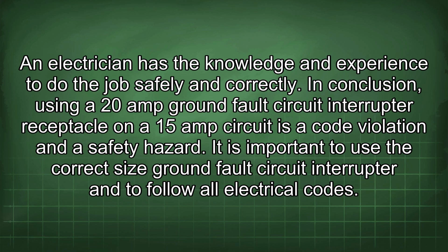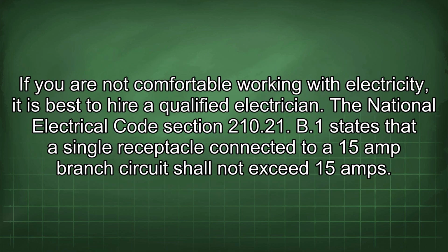In conclusion, using a 20 amp ground fault circuit interrupter receptacle on a 15 amp circuit is a code violation and a safety hazard. It is important to use the correct size ground fault circuit interrupter and to follow all electrical codes. If you are not comfortable working with electricity, it is best to hire a qualified electrician.